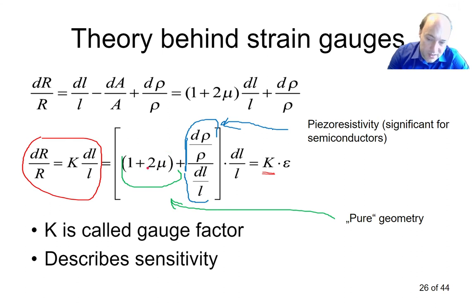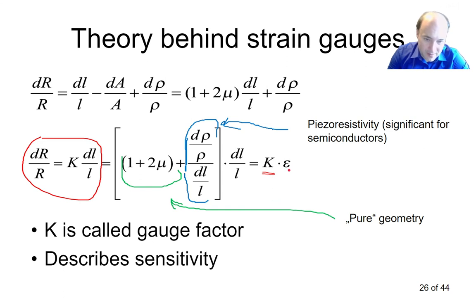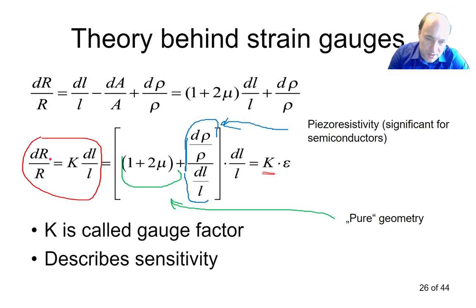For semiconductor strain gauges, both the geometric and piezoresistive contributions are present, with the piezoresistive effect dominant. Semiconductor strain gauges therefore have a non-linear dependence on strain and a very large dependence on temperature. For metallic strain gauges, K is approximately 2 and the response is linear, making them more straightforward to use in practice.